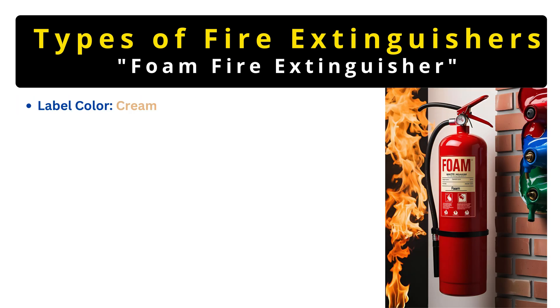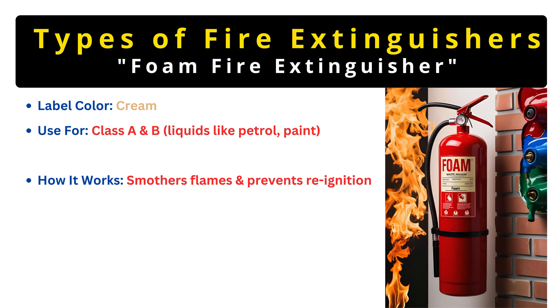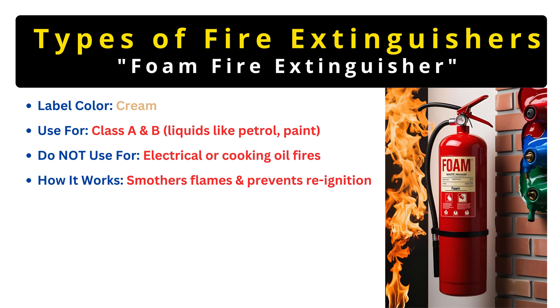Next, we have foam extinguishers, marked by their cream-colored label. These are a step up from water extinguishers because they can handle both Class A and Class B fires — ordinary materials and flammable liquids like petrol or paint. The foam smothers the fire, cutting off its oxygen supply while also cooling the fuel, making it great for things like a fuel spill fire in a garage. But foam is still mostly water-based, so don't use it on electrical fires, and it's not designed for cooking oils — that's what wet chemical extinguishers are for.